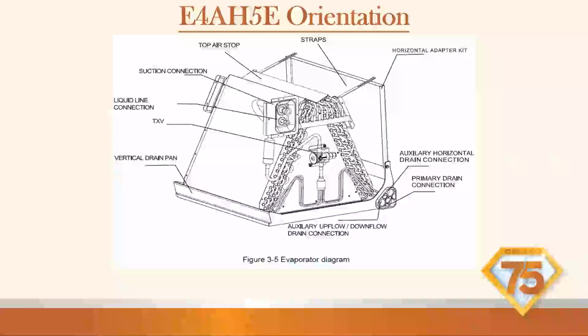There's our coil. There's that strainer we were talking about. So if that thing does get plugged up, we can take a temperature reading on either side, or both sides, and if there's anything over a 3-degree temperature split, it is plugged. So we're going to have to replace it.